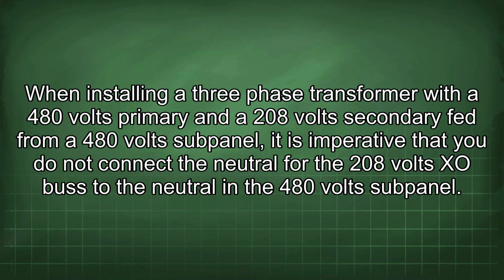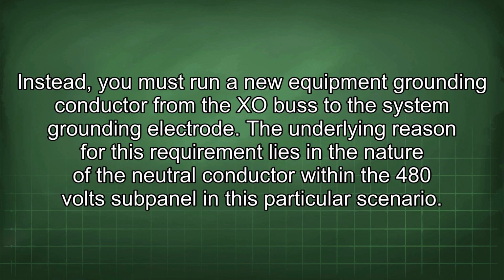When installing a three-phase transformer with a 480 volts primary and a 208 volts secondary fed from a 480 volts subpanel, it is imperative that you do not connect the neutral for the 208 volts XO bus to the neutral in the 480 volts subpanel. Instead, you must run a new equipment grounding conductor from the XO bus to the system grounding electrode.